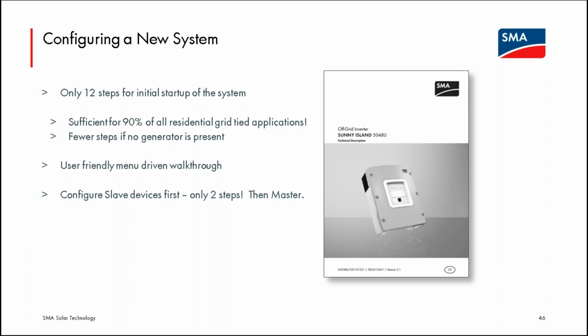Then it will ask for date and time. It'll ask, oh, am I connected to a grid or a generator? How much current should I pull from them? And a few more settings, but it's really only about a 10 or 11 step process, depending on your sources, for the master to be configured. And all of that information, what type of batteries they are, the amp hour capacity, will begin to fill out with default values, those 200 parameters for the Sunny Island system.